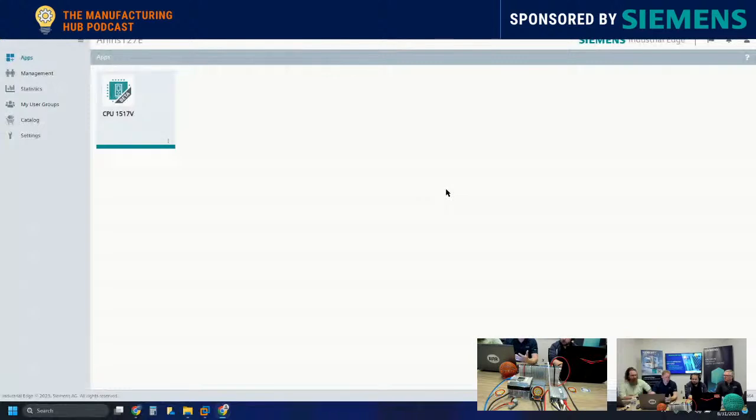Right. So work memory space, but you're not necessarily going to get sub-millisecond response time just because I'm sharing the resources of my PLC with other edge apps that are running on this edge device. And I guess we'll look into that, like the load, or you can see the load of, let's say, your IPC, and ultimately you can also scale up, right? That's why we have two different models. So depending on what you're running on top of the, let's call it the virtual PLC, you may want to upsize as necessary, right?